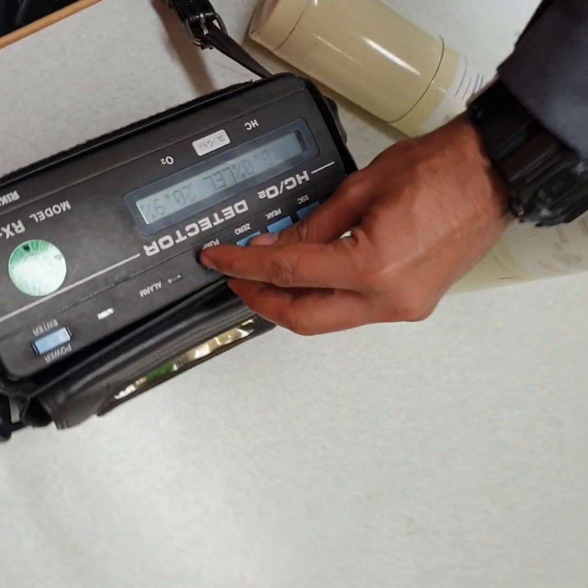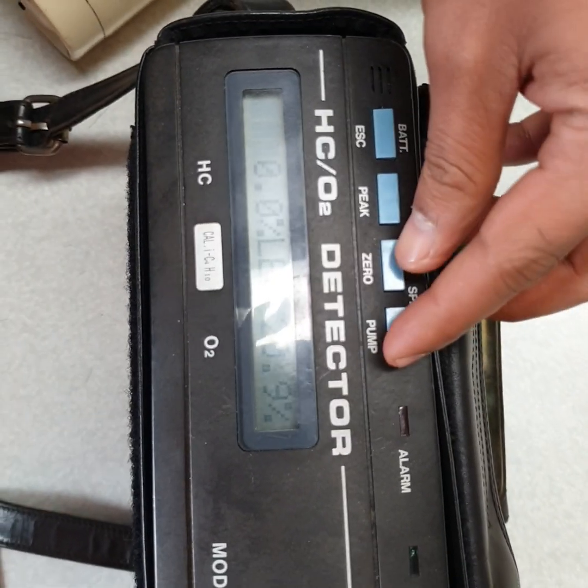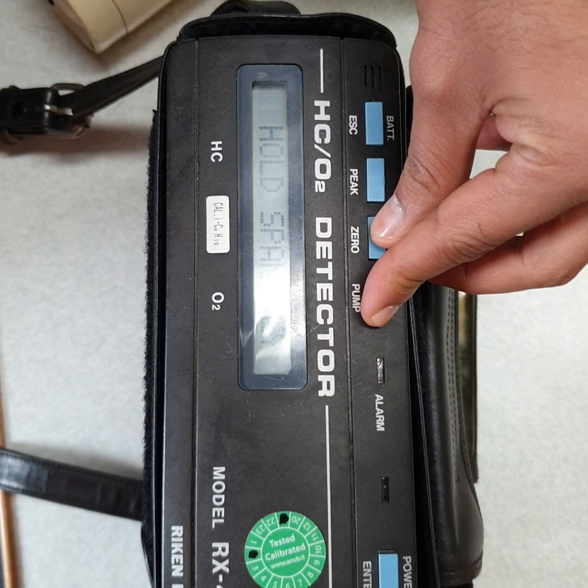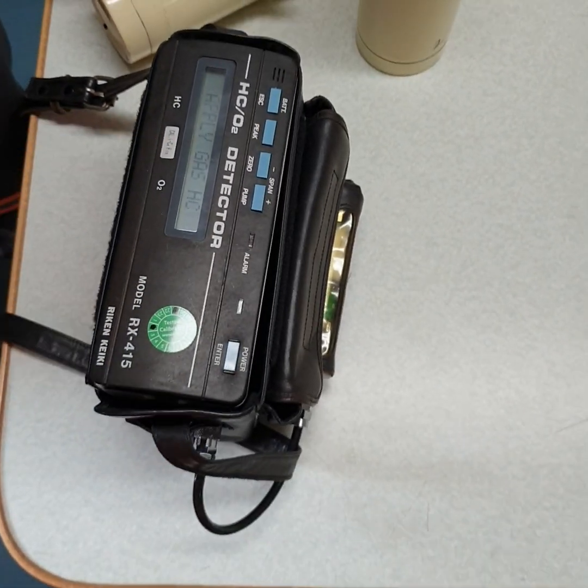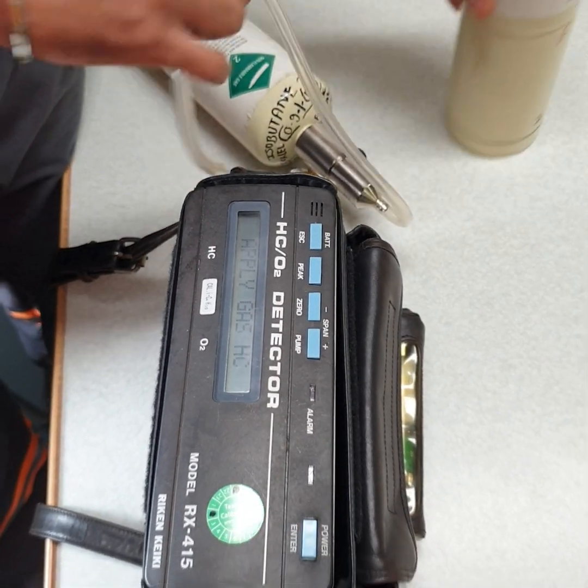Next, we will start calibration. To start calibration we have to first press these buttons — plus and minus, 0, and pump — for 3 seconds. Now it is telling us to apply HC gas, so apply isobutane first.